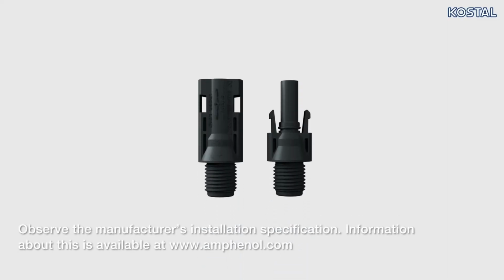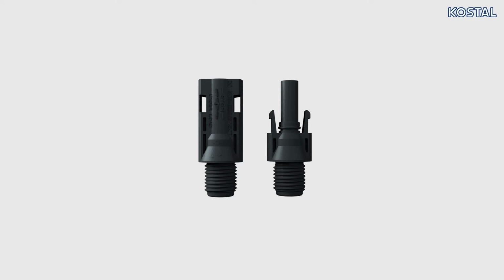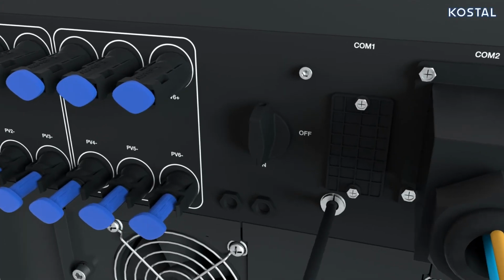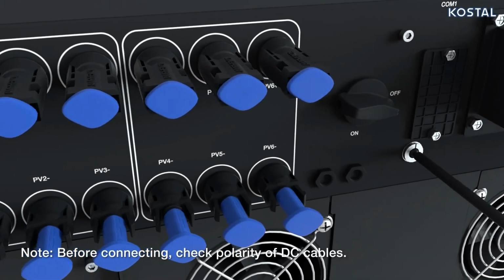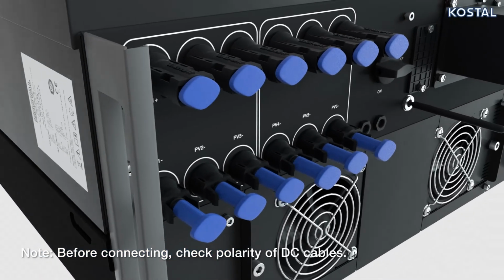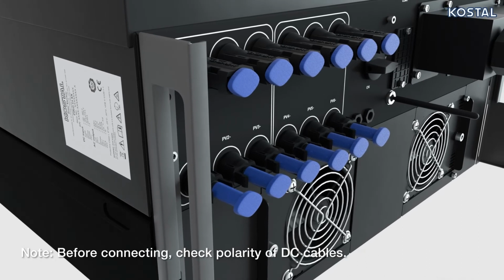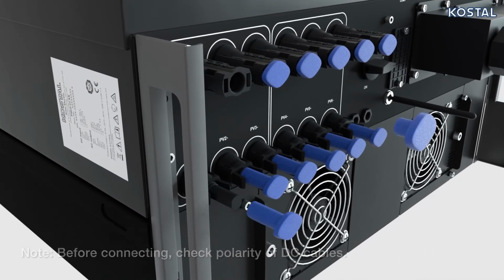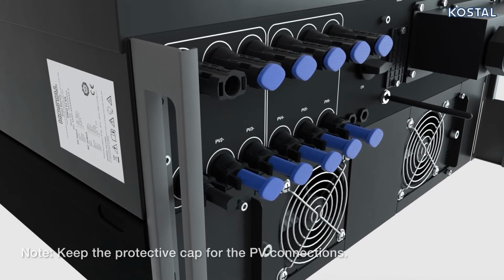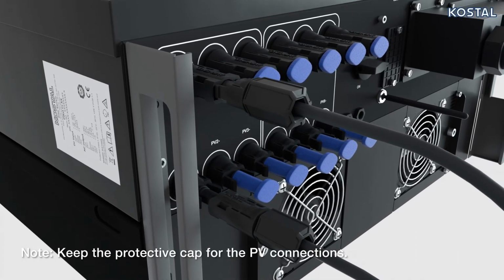Now connect the PV cables with the inverter. PIKO CI 30 uses Amphenol plug connectors of the type Helios H4. Turn the DC switch on the inverter to the off position. Remove blue protective caps from connection sockets and plug the pair of Amphenol H4 connectors onto the DC inputs until you hear them engaging.